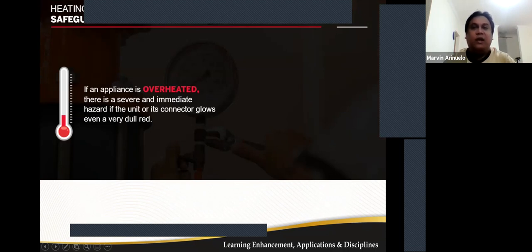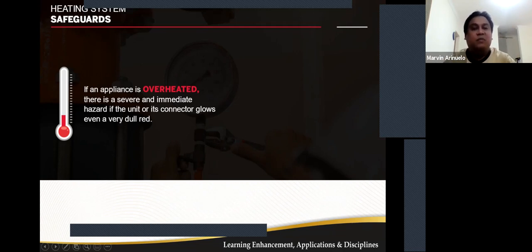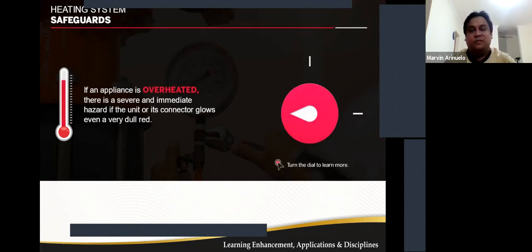According to the research, if the appliance is overheated, deliberately or through neglect, there is a severe and immediate hazard if the unit or its connector glows even in a very dull red. The control is simply to turn off the valve and close the door and air damper until things cool down.